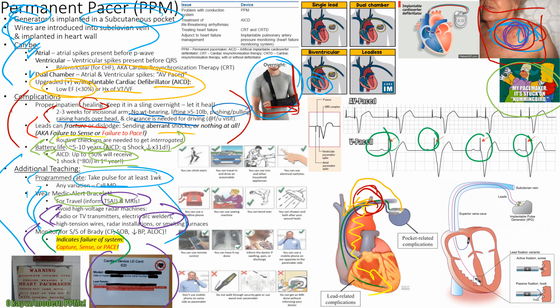If we're saying, well, there's no pacer spike there, then that might be a failure to pace, failure to capture, or failure to sense. So we have to look at these pacer spikes. If there's no pacer spike, that's actually called a failure to pace, okay? And we'll talk about that on the next slide.